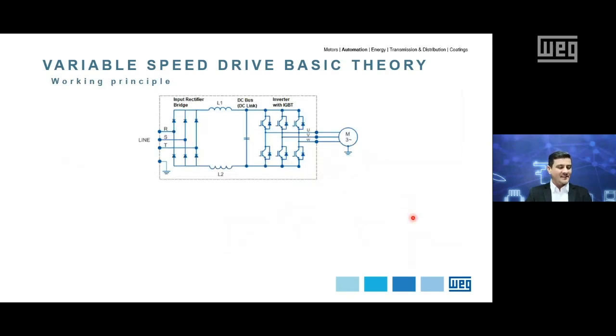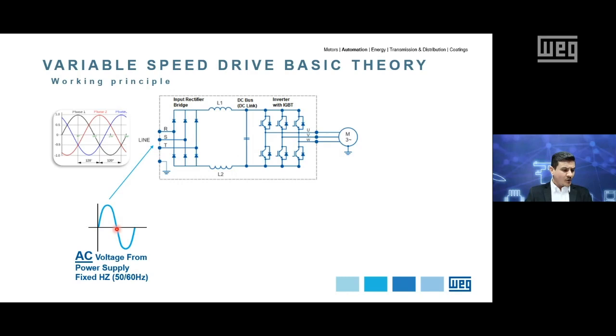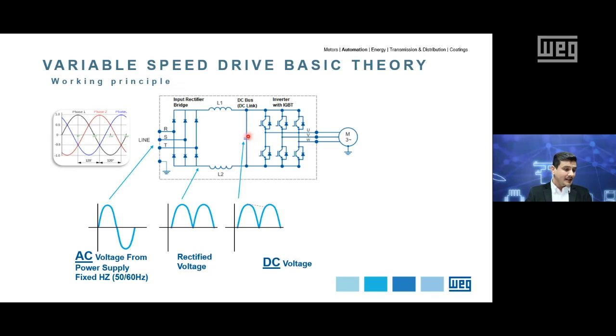So the working principle of a typical 6-pulse VSD can be divided into 3 main parts: the diode bridge, the DC link or DC bus, and the inverter unit. Firstly, the AC input voltage passes through the rectifier bridge, which is composed of 6 diodes. At this point, we have a rectified voltage. However, as you can see, the rectified voltage has ripples, and that's why the DC bus will smooth out these ripples. As a consequence, a DC voltage will be available at the inverter section.